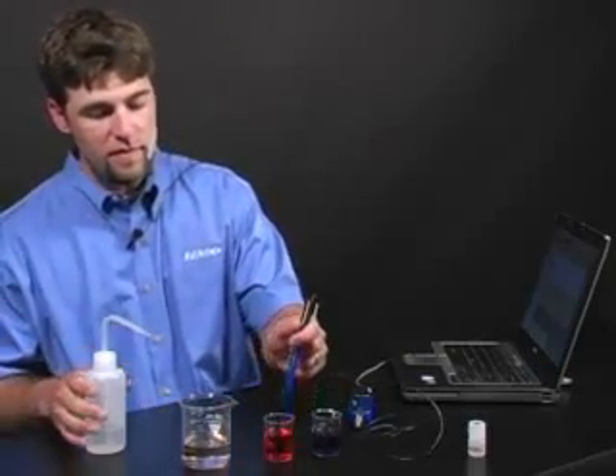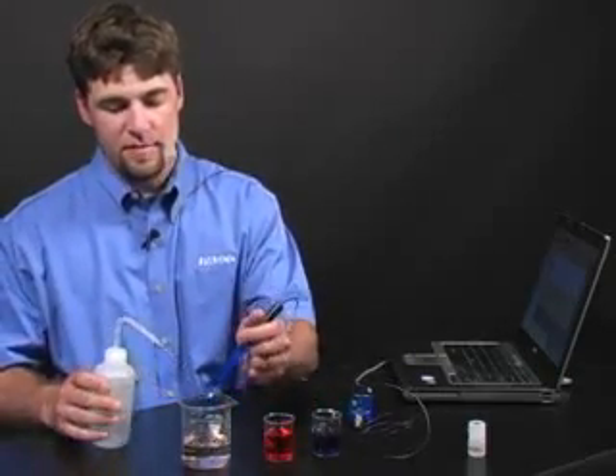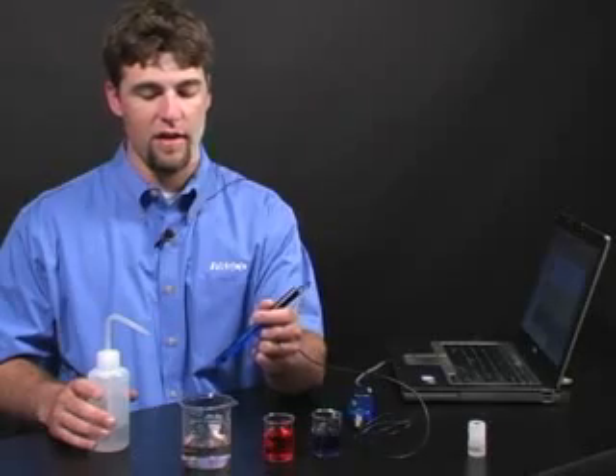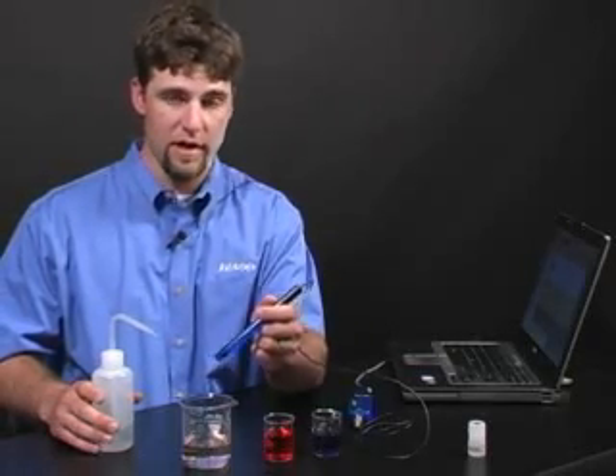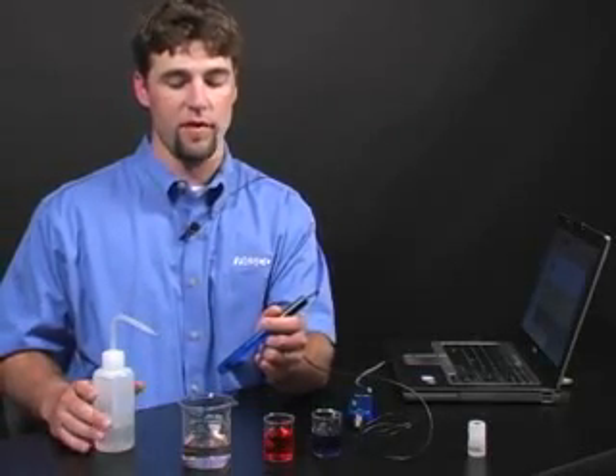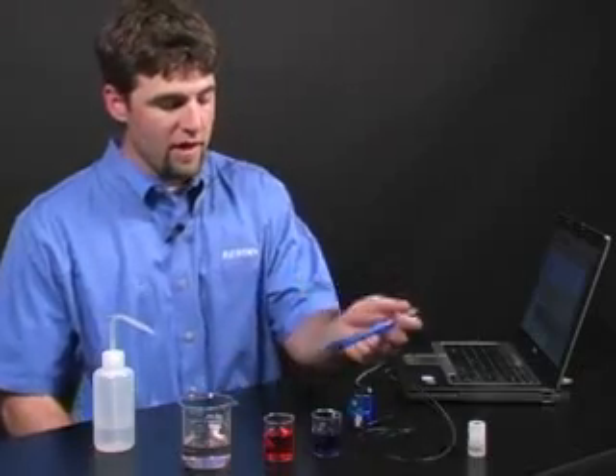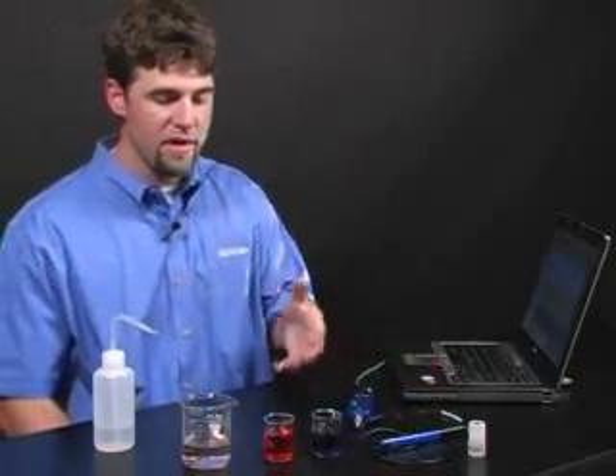It's important to note that sensors like this pH sensor have a finite shelf life and often require calibration. It's recommended that you calibrate this sensor before every experiment. It's also important to note that the calibration information that we've just recorded is not stored on the sensor itself, but in fact in the file that you'll save after having recorded data. And it's just that easy.